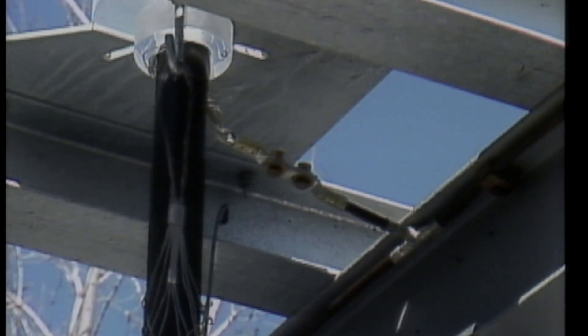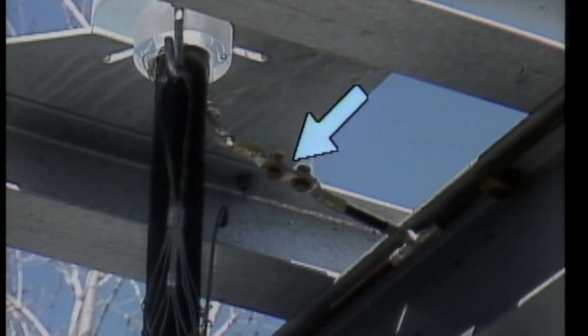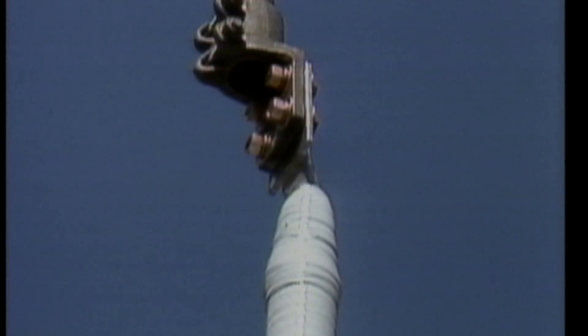The cable is raised into place. The bushing is installed in its mounting bracket. The cable is held in place by a support grip. The copper braid and neutral wires are connected to the system ground, and the termination connector is bolted to the bus connector.